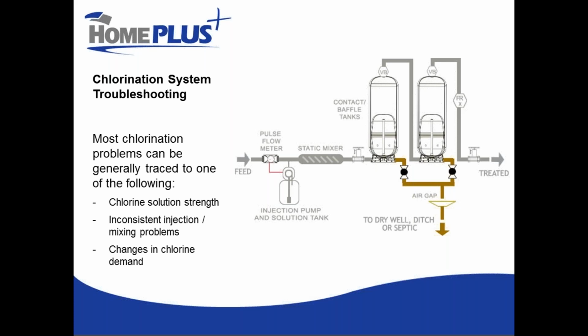We might have some sort of mixer, and then the water is generally sent to some sort of contact tank where we give the chlorine time to do its job, because chlorine does not act instantly. While it's doing its job, some of the chlorine is used up interacting with organic matter. Some of the chlorine is used up interacting with iron and manganese. Some is interacted with bacteria and other microorganisms. And coming out the other end is less chlorine than we put in. So what we put in is our total chlorine. What comes out is our residual chlorine. And what is used up is referred to as our chlorine demand.